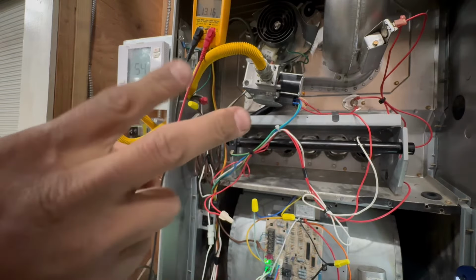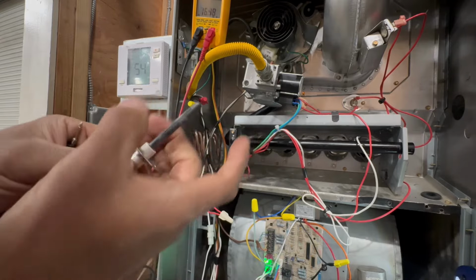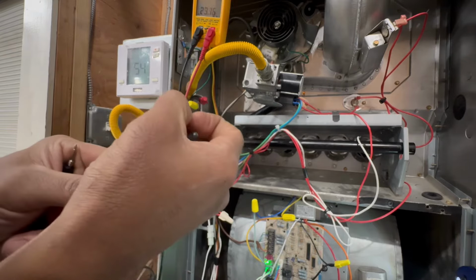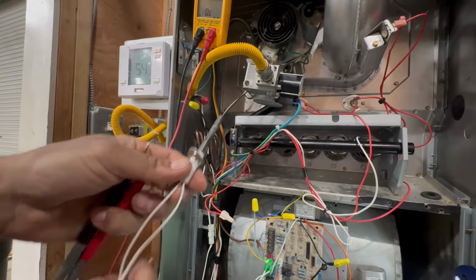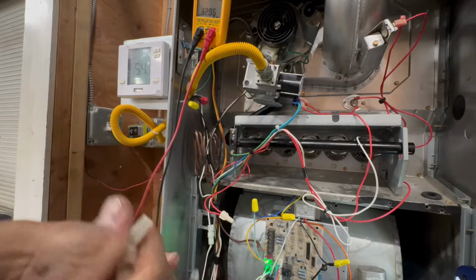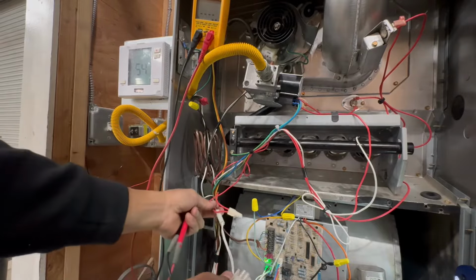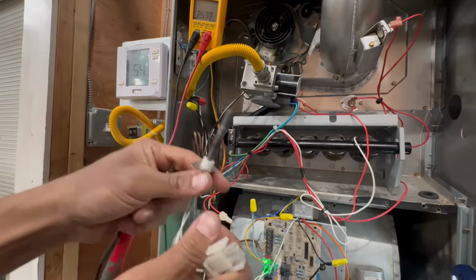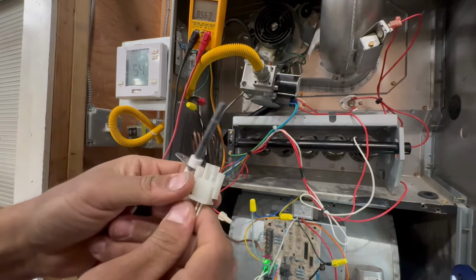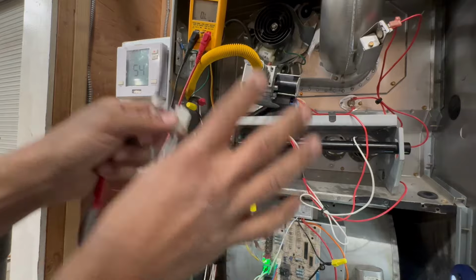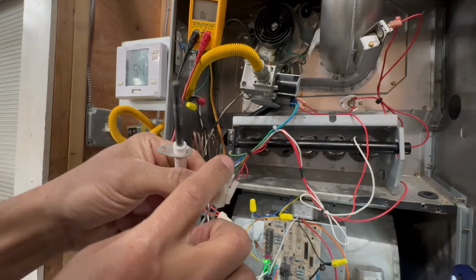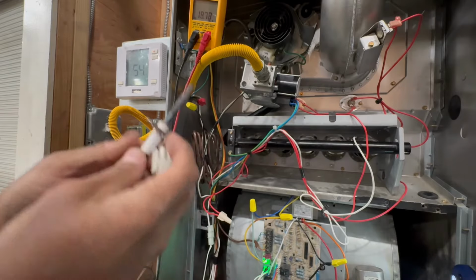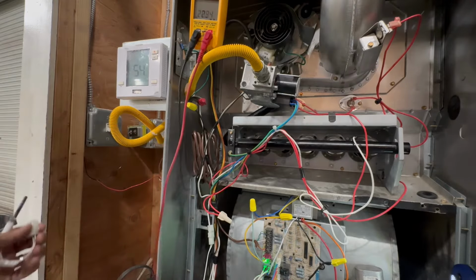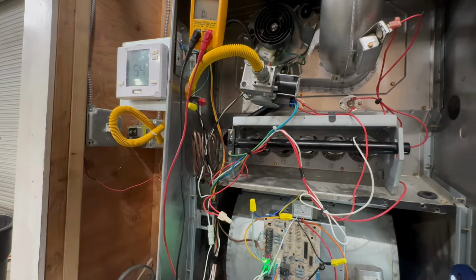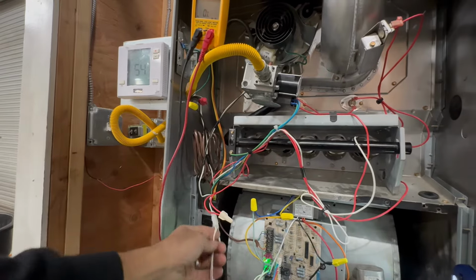You're like, wait, I thought hot and neutral can't touch each other. Well, we have a special part, a special element. It collects the heat. It turns cherry red for a couple seconds just to get that spark, and it works. That's how it works. So of course, if you also want to check, because it could happen that this hot surface igniter is not working properly, you have to turn off power, right? Obviously, turn off power, isolate it, and then ohm it out. And if it's good, then okay, it's not the hot surface igniter. You've got to make sure if the board is sending 120 volts. The board can go bad. It definitely can go bad.